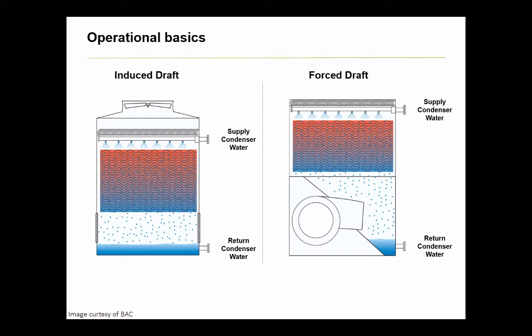These towers simply take a hot supply of condenser water, evaporate a portion of its heat to the atmosphere, and return the remaining cooler condenser water to the facility to be used again to absorb heat. First, hot water is sprayed down over a cooling tower material called fill, which is where the heat transfer takes place. The fill's purpose is effectively to increase the time the water and air cross paths.